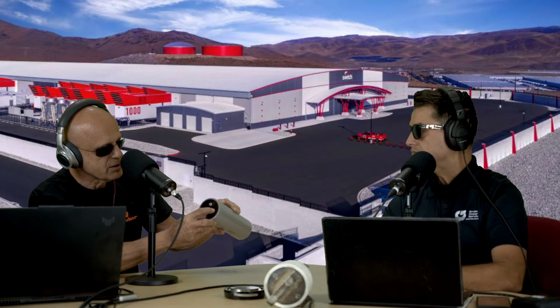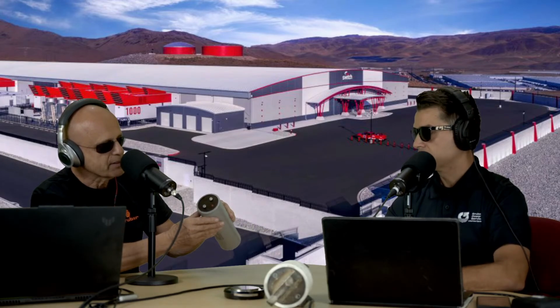In extreme cases, these things are responsible for thermal events, meaning this thing will catch fire. There's a little pressure release valve on here that typically will begin to manifest if there's a problem, and that's the reason you want to make sure you're doing preventive maintenance on your critical power equipment, because our field engineers look for things like this. They look at age, they look at that little vent cap, and that's the reason you want to replace those. I sell these all the time.